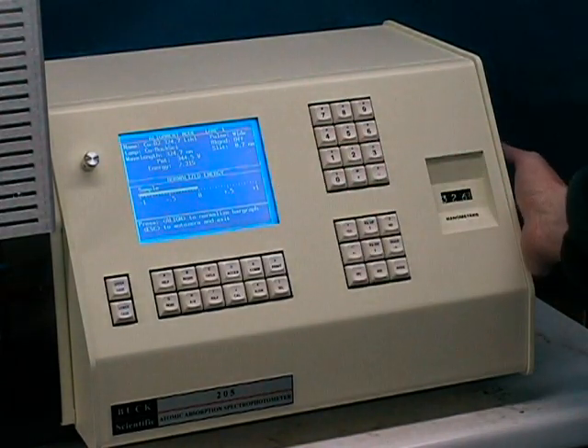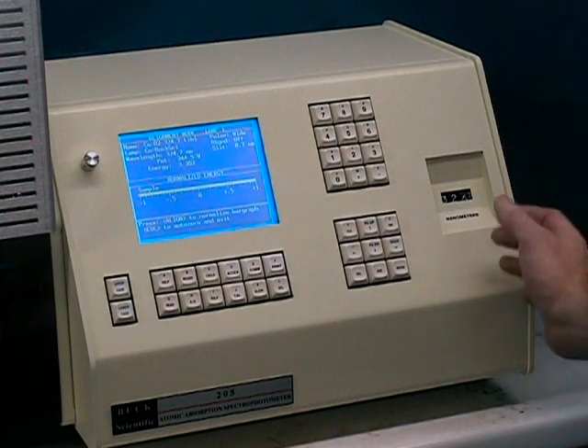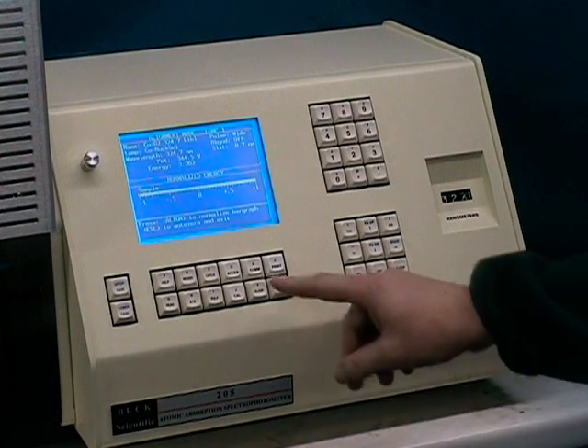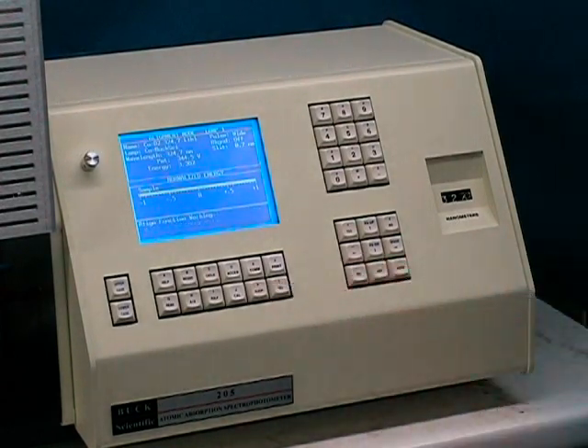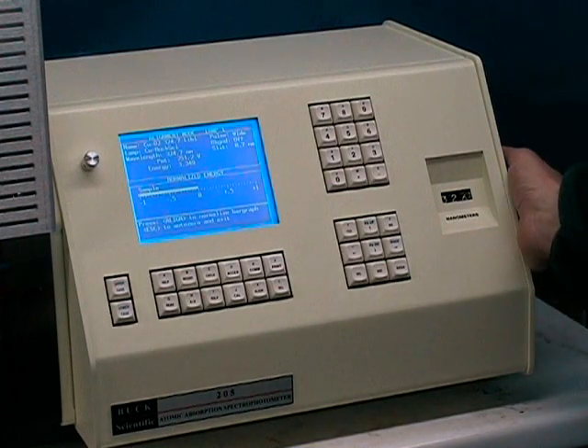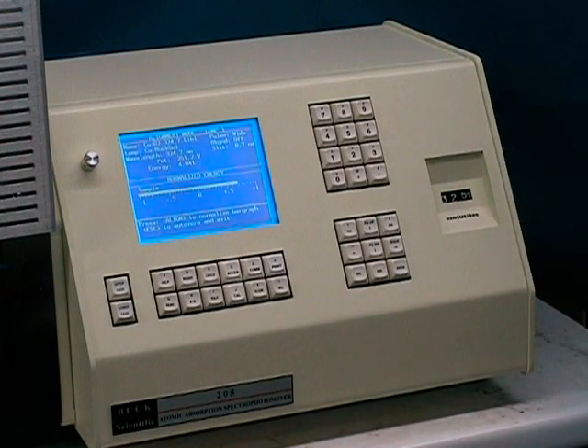As you rotate the wavelength adjustment knob, the bar graph may go off scale, depending upon how it's set. You may bring this back to the center point by pressing the Align key, which normalizes the position of the bar graph. Continue to make your adjustments, but please be aware it is not necessary that the end of the bar be at the 0 position. It just must be somewhere on the screen display. Once you have set the wavelength to get the optimum results in your analysis, you will also want to adjust the position of the lamp to see if you can optimize the energy even further.